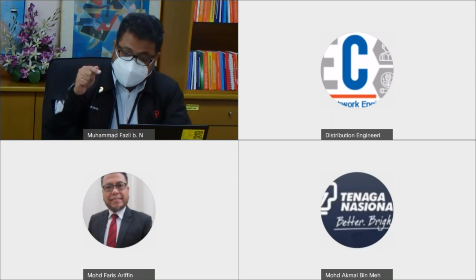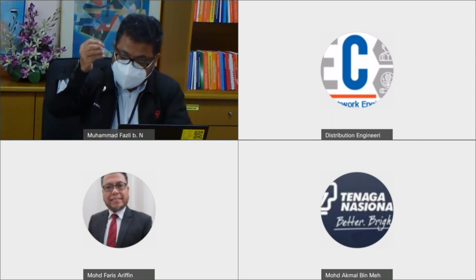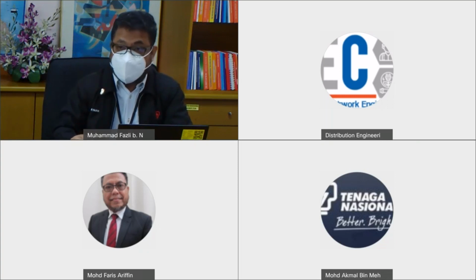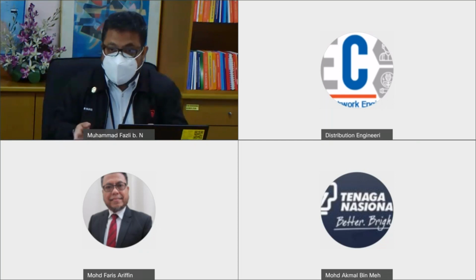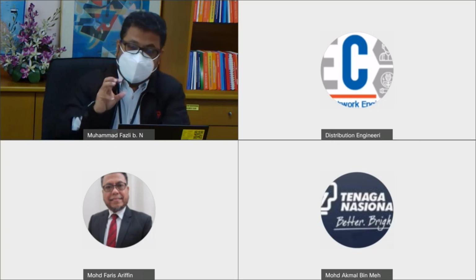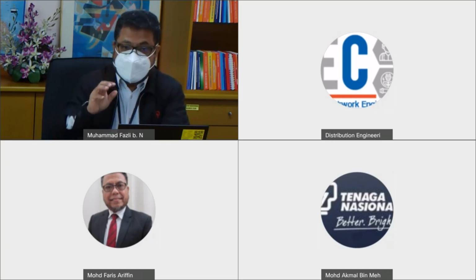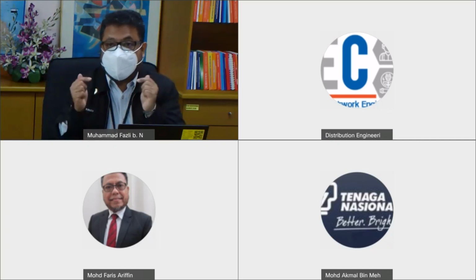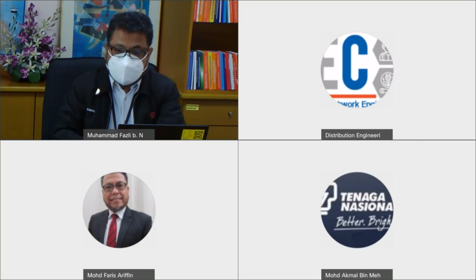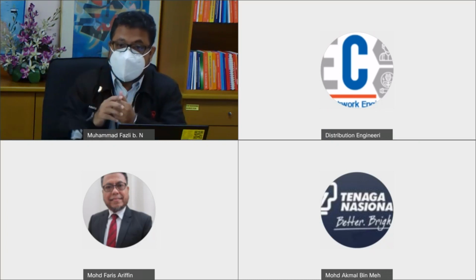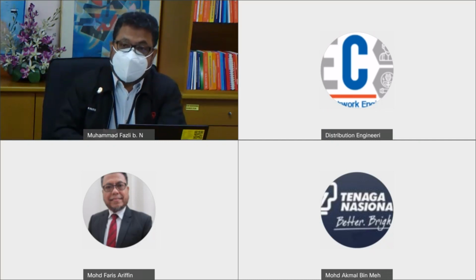So lightning hits the shield wire, for example, and it will travel along the steel structure of the pole or the tower, and it needs to be dissipated to ground. But what if the tower footing resistance or pole footing resistance is not good enough to dissipate the lightning current? It will go up again through the steel structure and try to hit the weak points, and the weak points will be the arcing horns, or even the insulator string. That will cause a back flashover and cause the line to trip, developing into fault current that is seen by our protective relay as a fault. Then that would cause the system to interrupt.